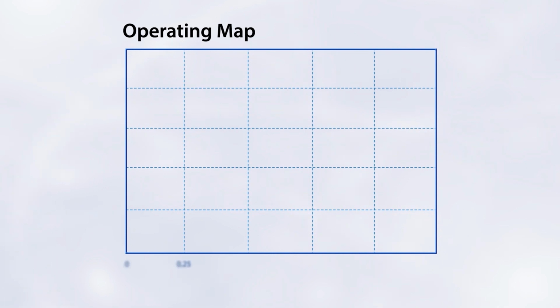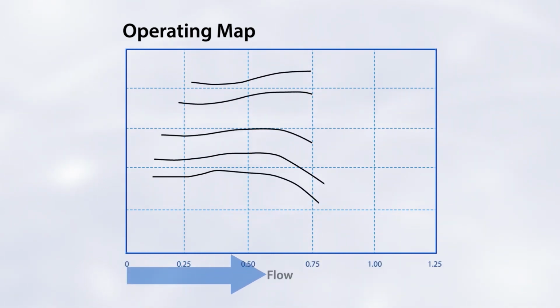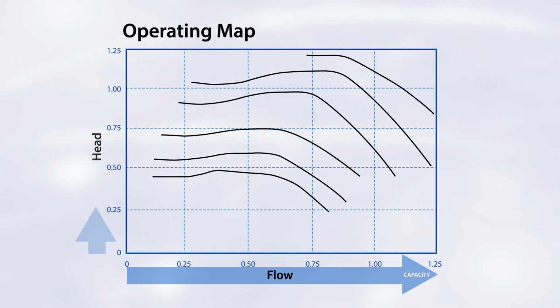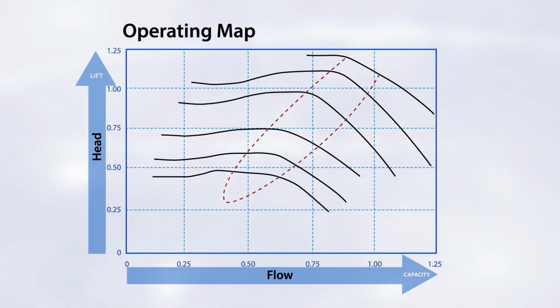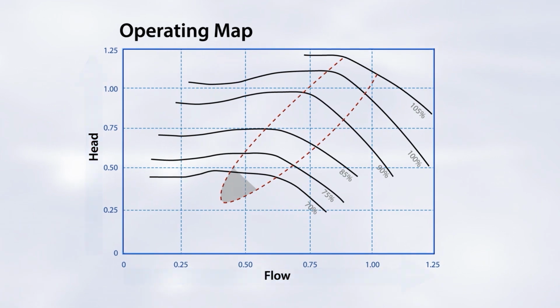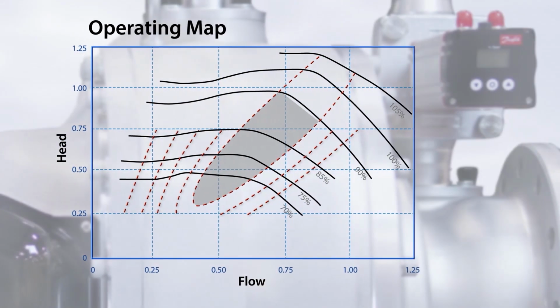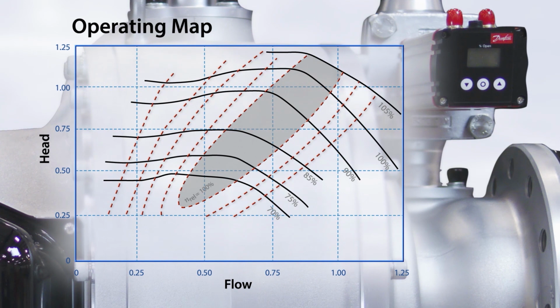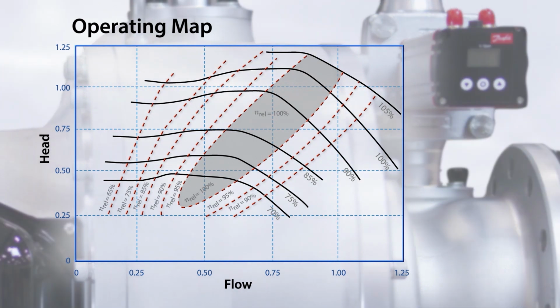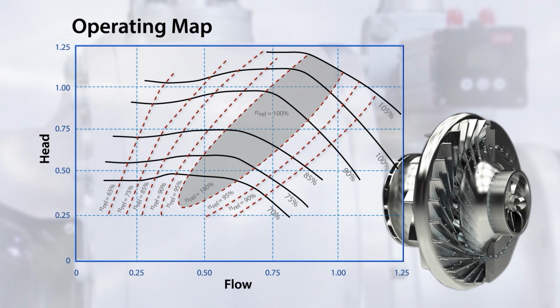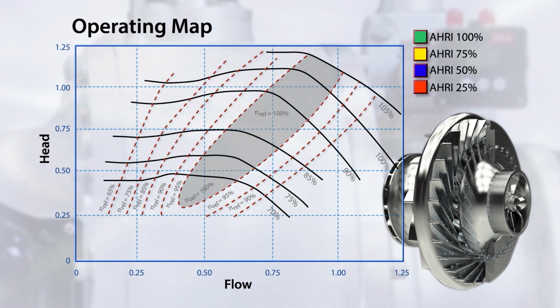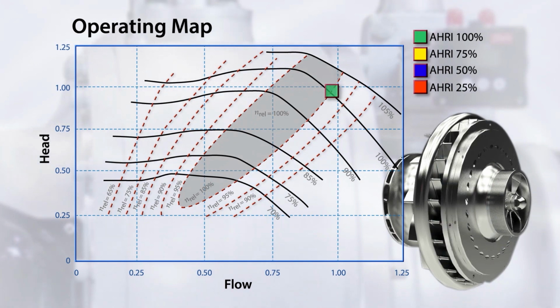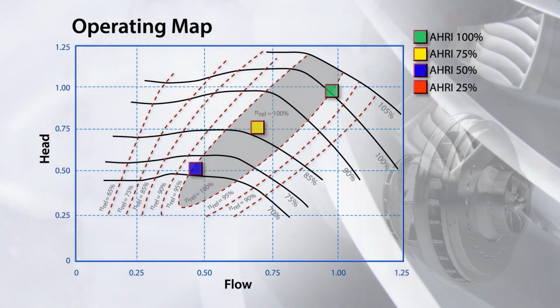The centrifugal operating map illustration shows in relative terms the compressor flow, which corresponds to capacity, and head, which corresponds to lift for specific differential temperature applications. The large oval-shaped peak efficiency islands for the VTT compressor enable it to operate at peak performance over a large range of load and lift conditions. The VTT series impeller and aero designs place the optimal 100% AHRI design point within the 100% relative efficiency island. The design also delivers the peak efficiency for the critical 75% and 50% part load points for optimized efficiency.